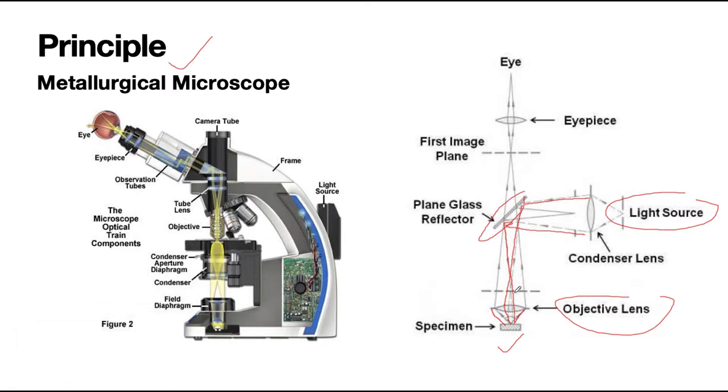So some of these lights which fall on the specimen get reflected from the specimen surface and will be magnified and pass through the plane glass reflector and magnified again by the upper lens of the system. This is the upper lens of the system and the magnified image can be seen through the eyepiece. So this is how a metallurgical microscope works.